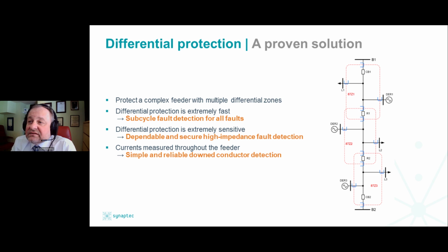So assume for a second that you are able to put current transformers at key points along the complex feeder. Those current transformers provide signals to substations, and those signals are real-time, high-fidelity signals. It is as if you had long secondary cables that deliver that signal all the way to the substation. You know that you could do a much better job protecting that feeder. Differential protection is extremely fast, so you will have a sub-cycle fault detection time for all faults, regardless of their location. Differential protection is extremely sensitive, so now we are going to trip high impedance faults such as tree contacts.